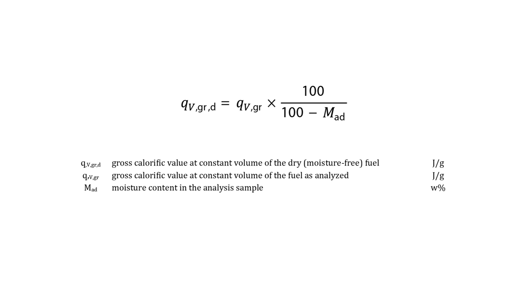As the moisture content of the actual analysis sample is of interest merely in connection with the calculation to the other bases, it is recommended to calculate a value of the gross calorific value at constant volume for the dry fuel using the following equation.